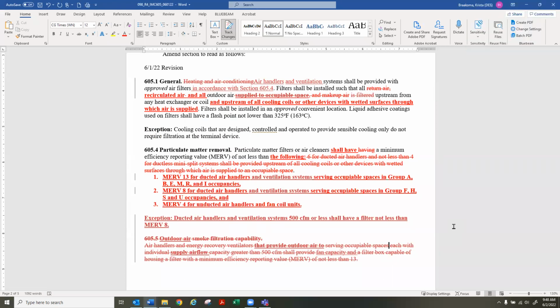So a question here, let's say you have an ERV that's integrated with an air handler. The way that 605.1 is written right now, let's say it's a group R occupancy and it's 501 CFM, you would have to put your MERV 13 filter upstream of the ERV heat exchanger or coil, I guess is what it says. My concern is that you might have to double filter the air. You might have to filter it before the ERV heat exchanger and then put another MERV 13 filter before the air handler, which isn't really necessary.